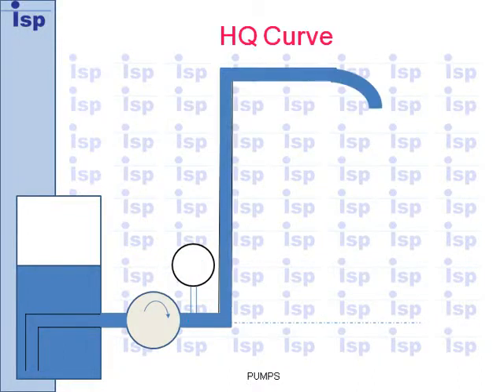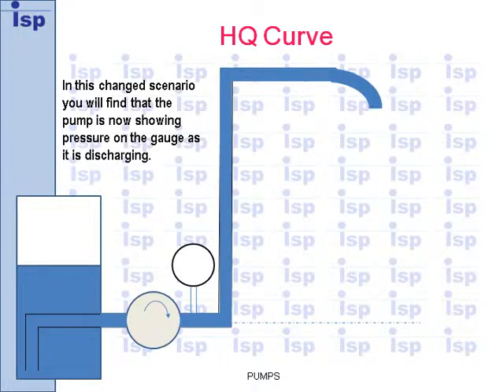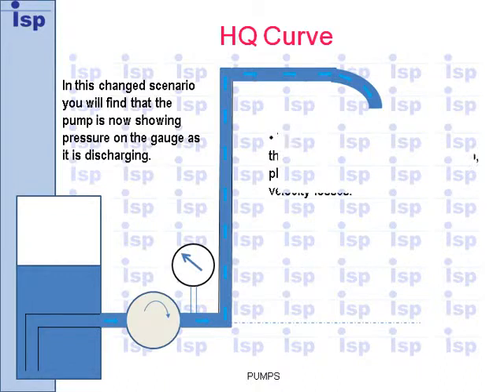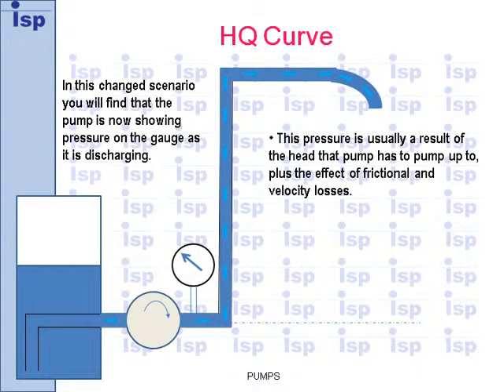In this changed scenario, you will find that the pump is now showing pressure on the gauge as it is discharging. This pressure is usually a result of the head that the pump has to pump up to, plus the effect of frictional and velocity losses.